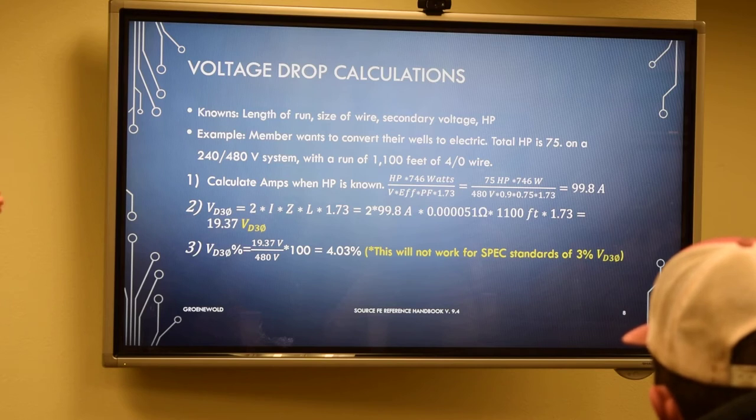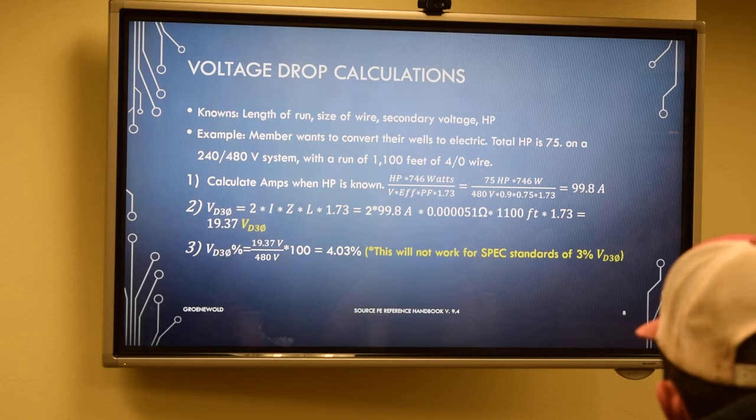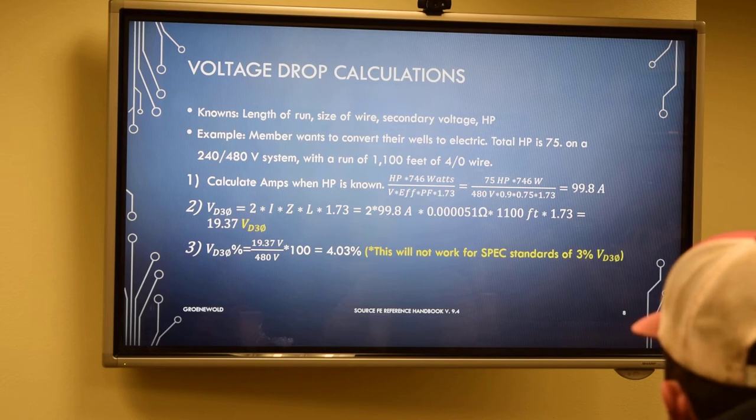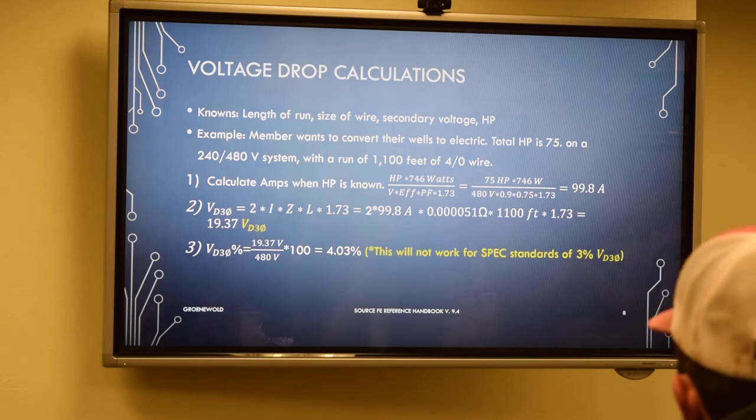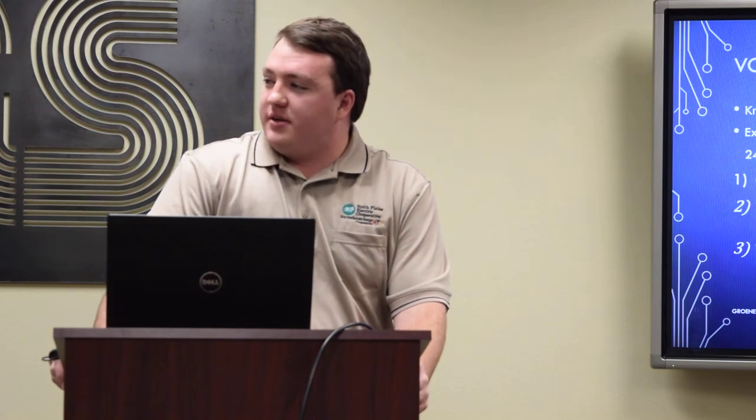Step two is where you start going into your voltage drop. Two times your current, times your impedance of the wire, times the length of the run, times that square root three, the 1.73. Any time, for example, the 4/0 wire, that is a known impedance and you can look that up. That's where that number 0.000051 ohms comes from. Once you plug into that equation right there, you'll get a voltage drop of 19.37 volts off of the 480. And to get it to the percentage, just divide that 19.37, divide by the 480, and then multiply by 100 to get into your percentage, where you get the 4.03%.